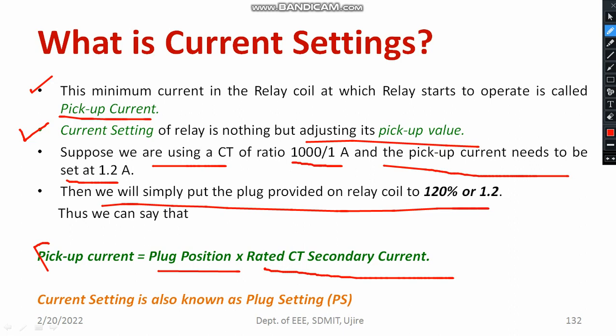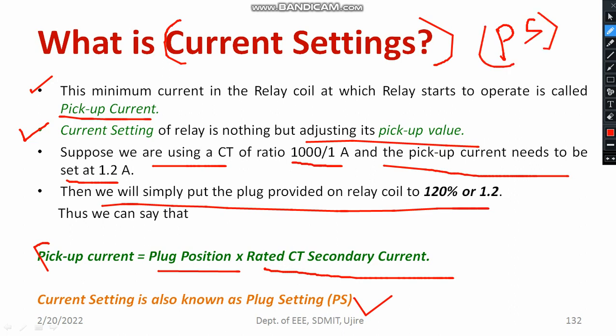Current setting is also known as plug setting, denoted by the letters PS. We need to consider the CT ratio and understand the pickup value — plug position multiplied by the rated CT secondary gives you the pickup current. That is why we get the particular value of pickup current in this manner.